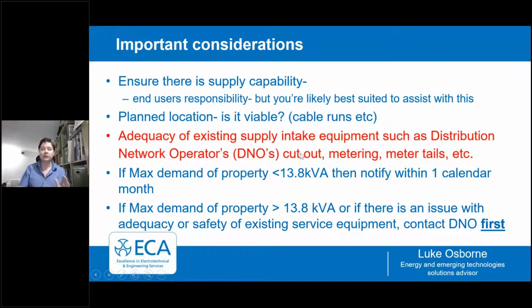So you need to make sure that the DNO cutout, the metering and the meter tails are in a good, suitable condition. And if they're not, you need to notify the DNO before you do any install work. If you deem that the maximum demand of the property is going to be less than 13.8 kVA, essentially 60 amps, you can install and then notify the DNO within 1 calendar month. So you can go ahead, install the EV charge point, and then make a DNO application. There's one form that they use, which is for electric vehicle charge points and heat pumps. It's the same form. You can find that on the ENA website, or you can consult the relevant DNO and get it from their website as well.